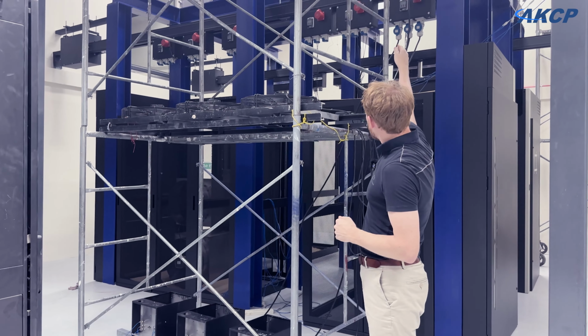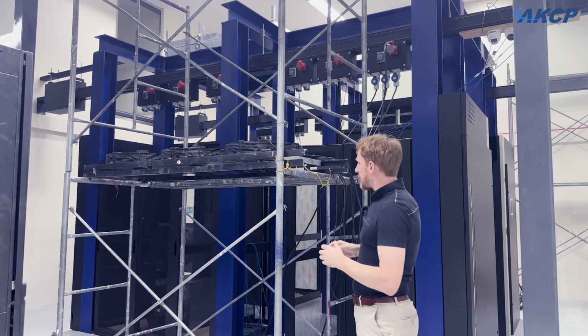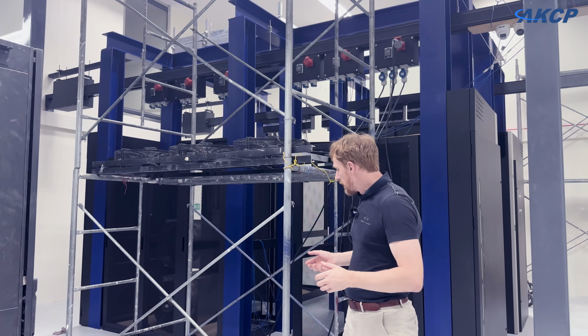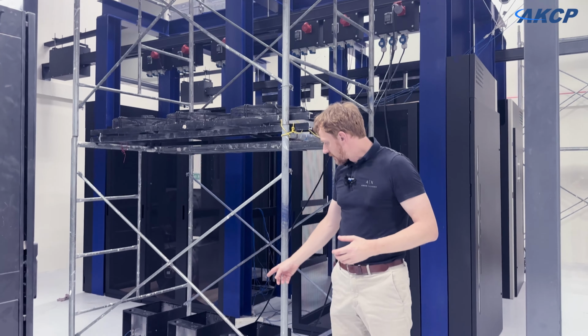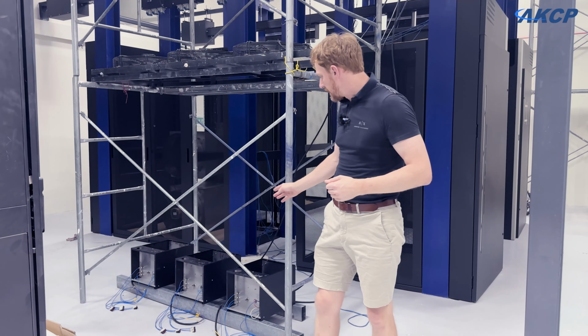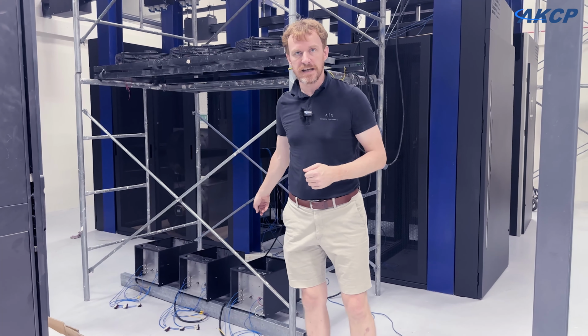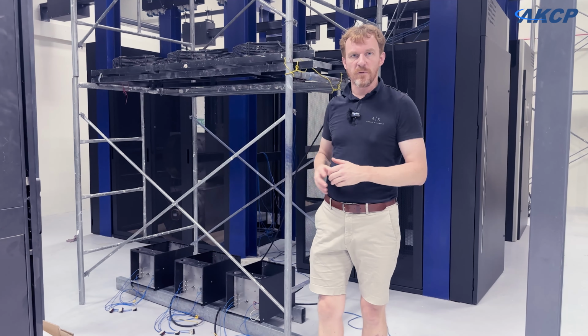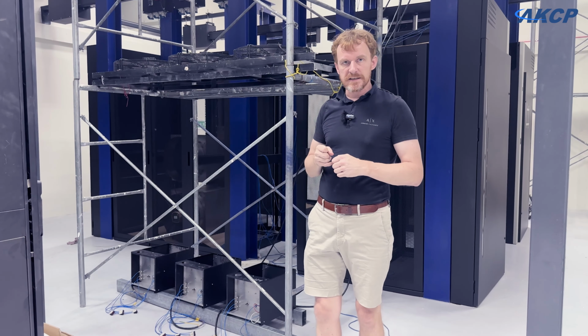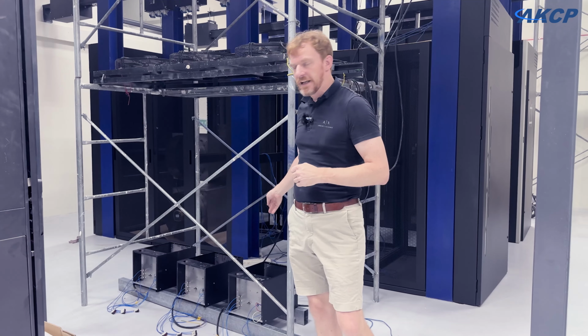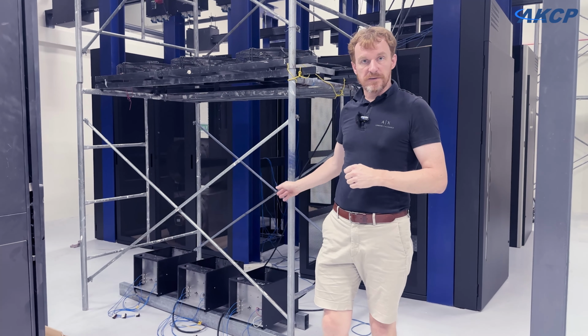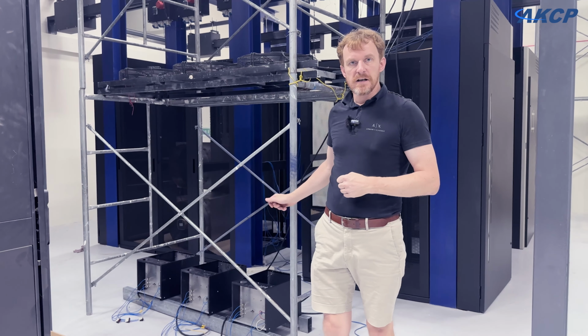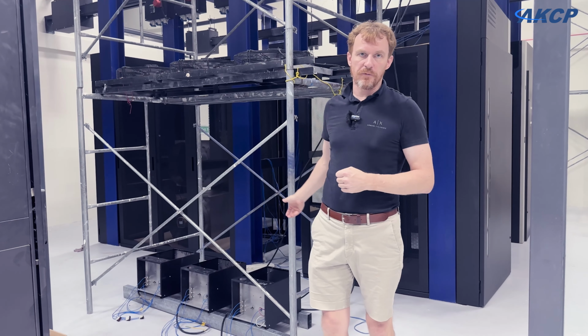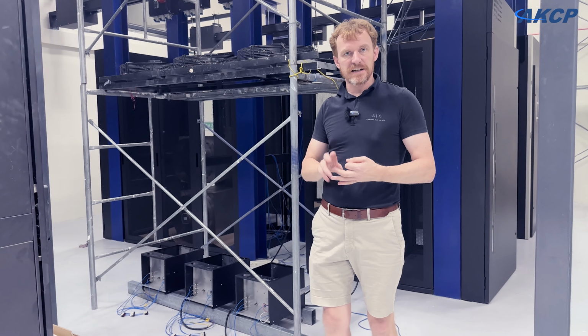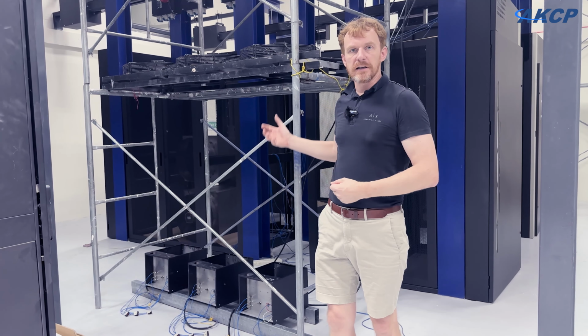Those are being powered by our overhead bus bars. So we're just testing out, now that we've got the power connected today, that this is all working. We've got individual switches on these heaters, on the individual heating elements. These are 3-phase heaters, and we've wired them 1 heating element per phase. So in a 9-kilowatt heater, we've got 3 3-kilowatt heating elements. And we can turn those on and off, so I can operate one of these heaters at either 3, 6, or 9 kilowatts. So we can adjust the loads in the racks through those switches.